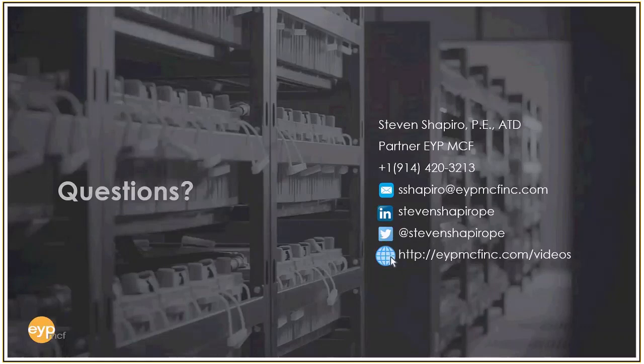And in those UL listed configurations, you need to have separation from one plant to the next. So if you had 3 UPS systems in one room, you couldn't necessarily have those batteries back to back. You'd have to have a spacing between them. And if it's not UL listed, then it's a different application. And so there's a whole group of presentations that are available on 855 and their impact. I know there's a lot of talk about 855 in the NFPA chat rooms, and we haven't seen how it's ultimately going to fall out yet.